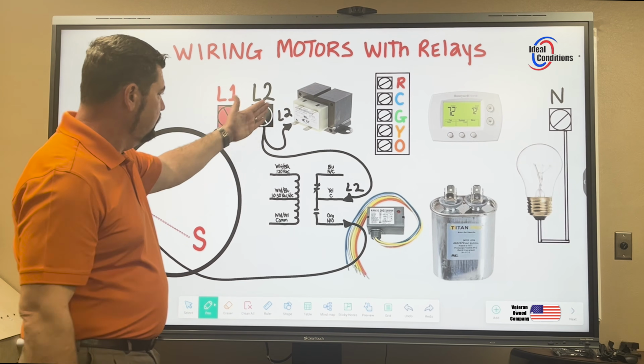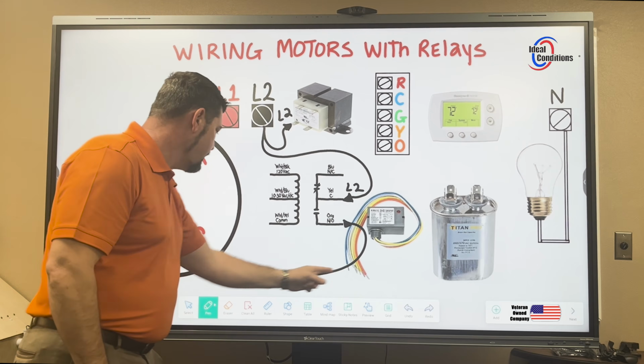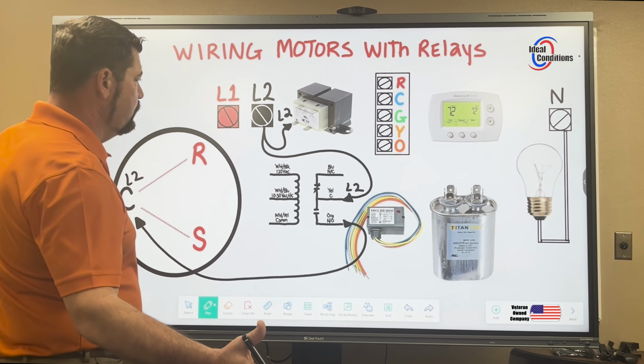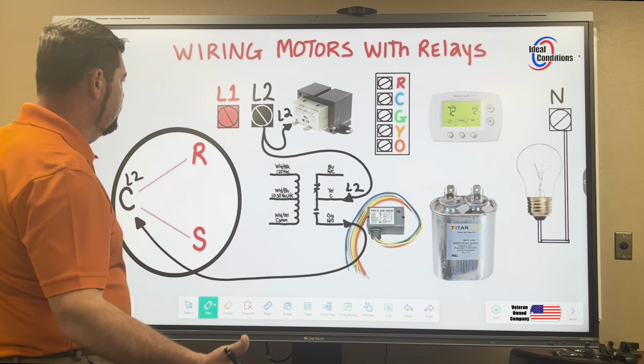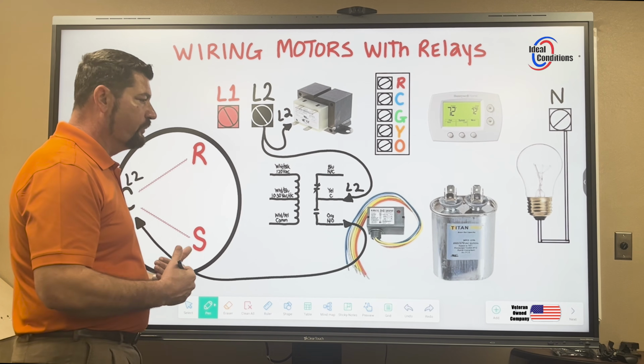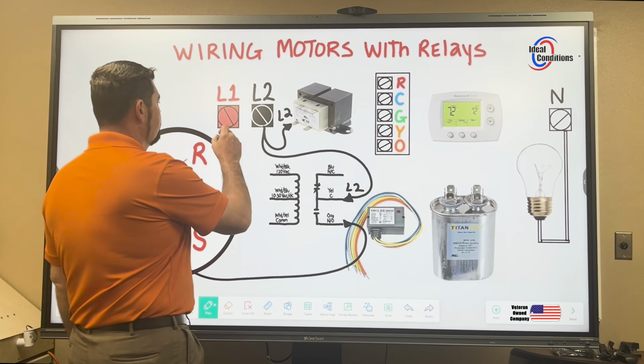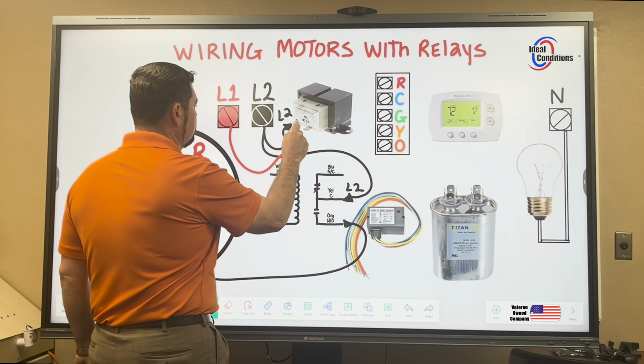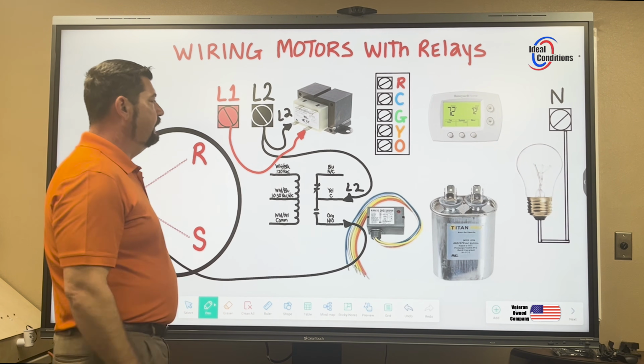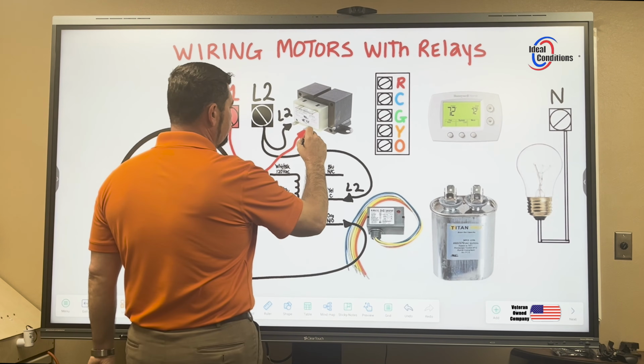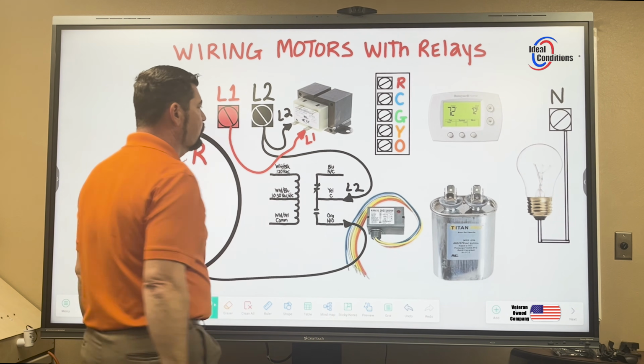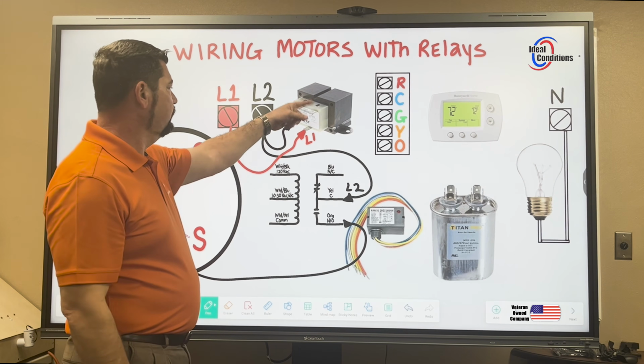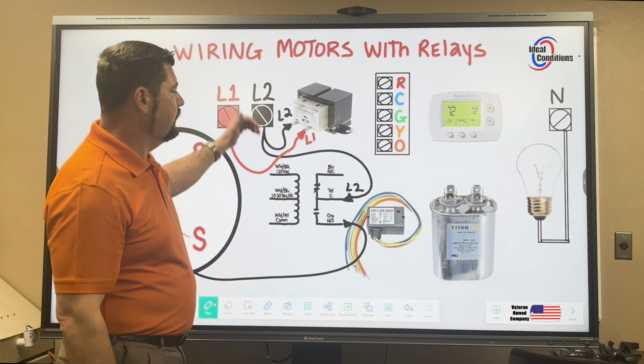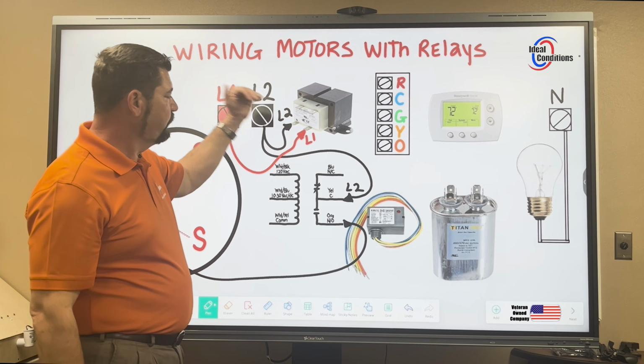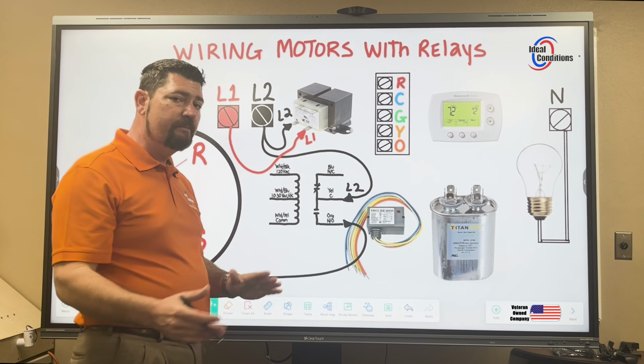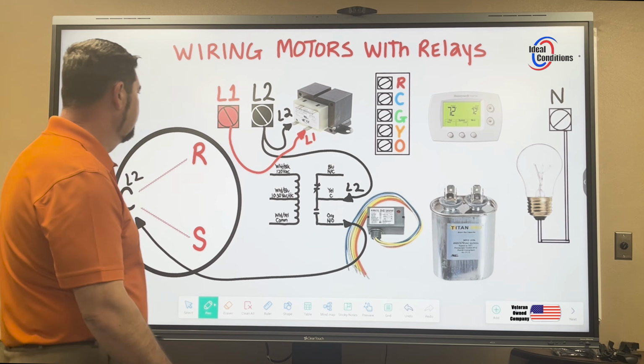So again, we're going to inspect. L2 check, L2 check, out of here, L2 check. Nowhere else does L2 have to be present. Now I can safely work on the other leg of power. So we're going to come over here. We're going to come out of L1. We're going to land power on the line side of the transformer. Okay, it says line here, it says load here. Well, L1 and L2, that is line. So now our transformer on the high voltage side is complete. Transformer's not complete, but on the high voltage side, it is complete.